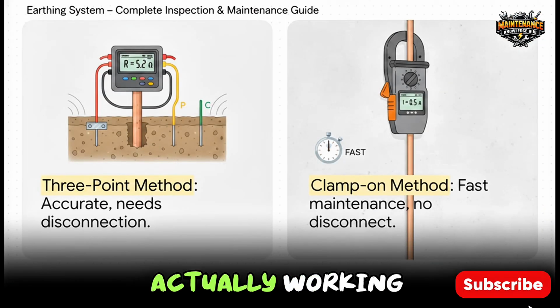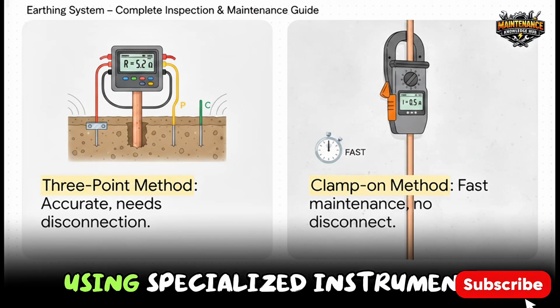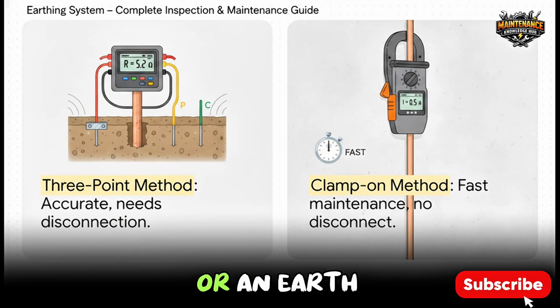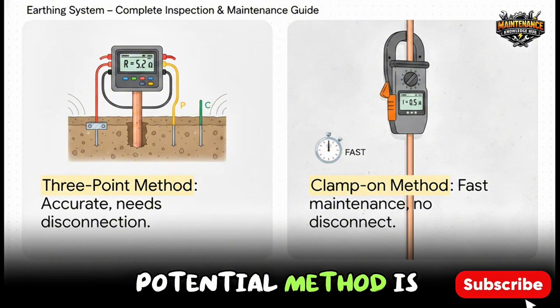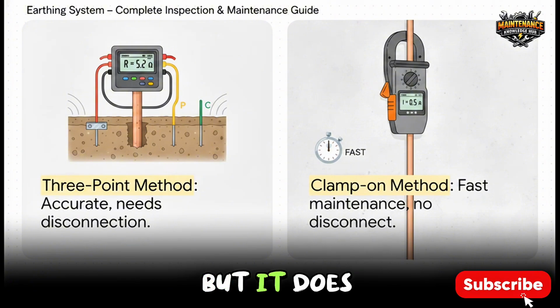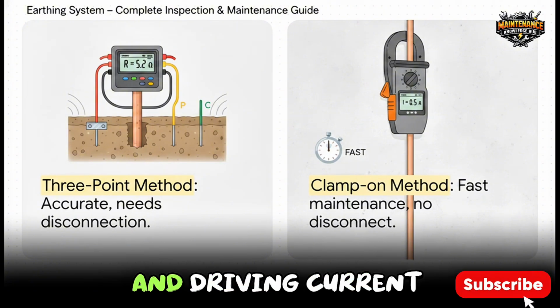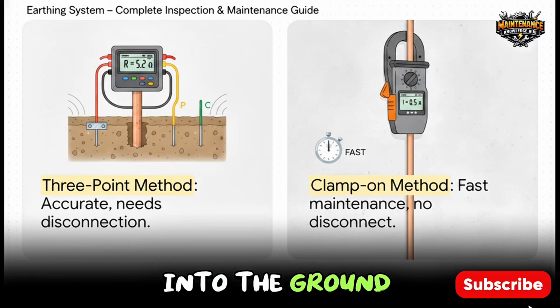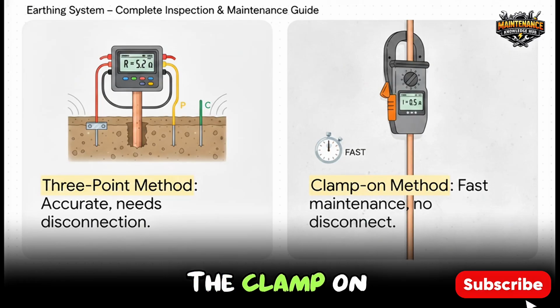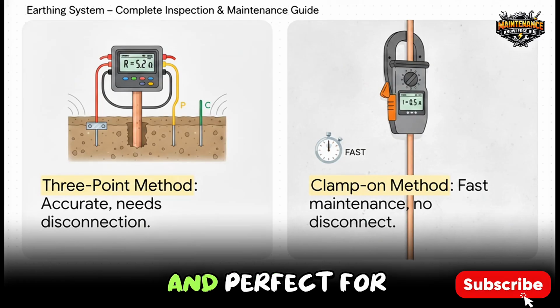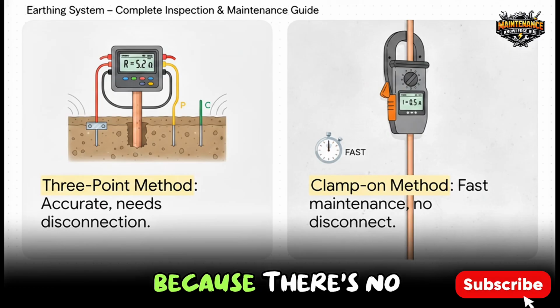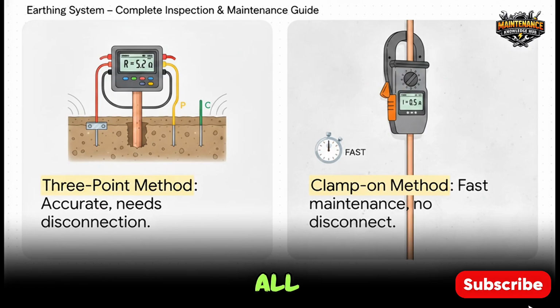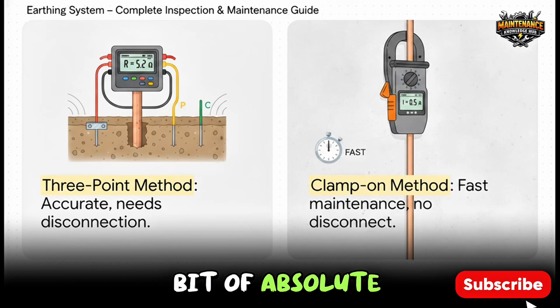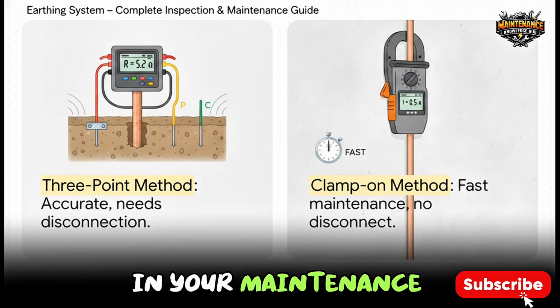So how do we know it's actually working? We test it using specialized instruments like a Megger or an earth resistance tester. There are two main ways to go about this. The 3-point, or fall of potential method, is highly accurate, but it does require disconnecting the earth electrode and driving current and potential spikes into the ground. On the other hand, the clamp-on method is incredibly fast and perfect for routine maintenance, simply because there's no need to disconnect the earth at all.